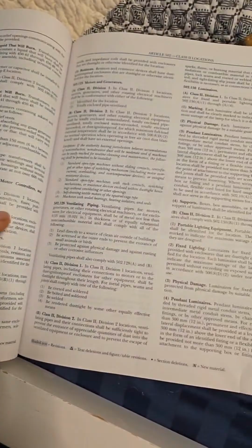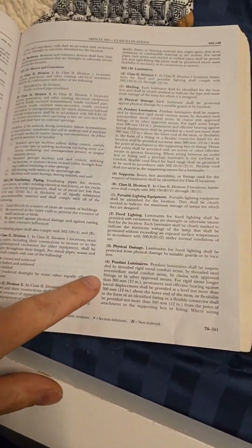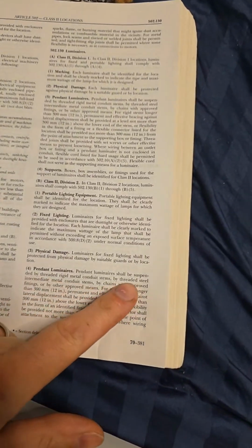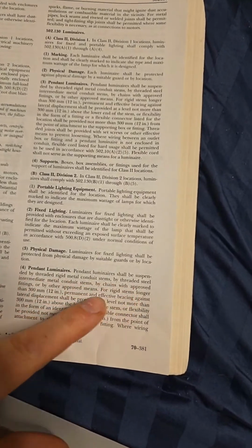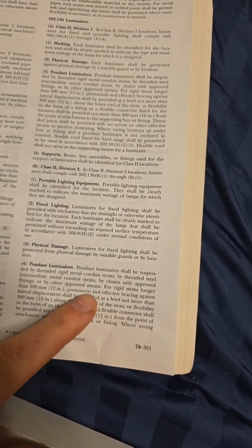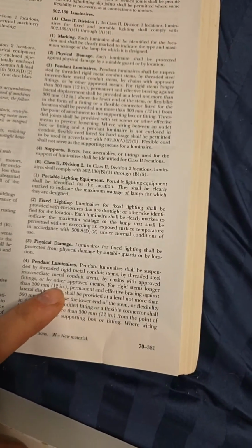Class 2, Division 1, ventilation, pendant luminaires shall be suspended by threaded steel, 12 inches, for rigid stems longer than 12 inches. We're going with 12 inches. I see 12 inches right there. Let's go 12 inches.